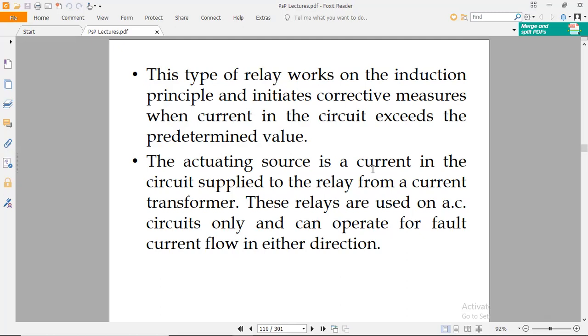The actuating source is the current in the circuit, supplied to the relay from a current transformer. These relays are used on AC circuits only and can operate for fault current flow in either direction, meaning in the forward or reverse direction, through the rotation of the core of the relay coil.